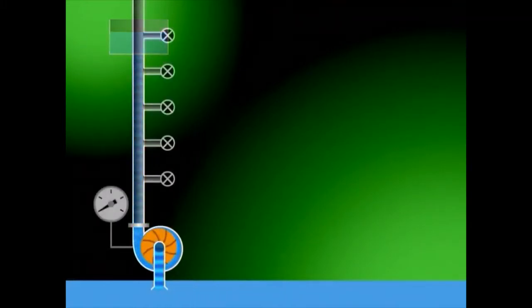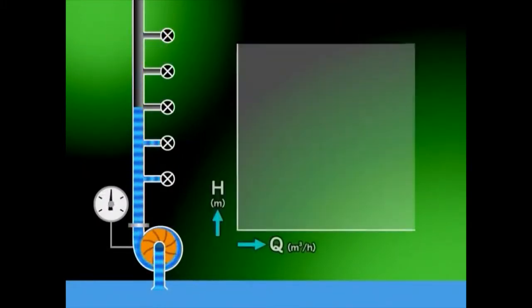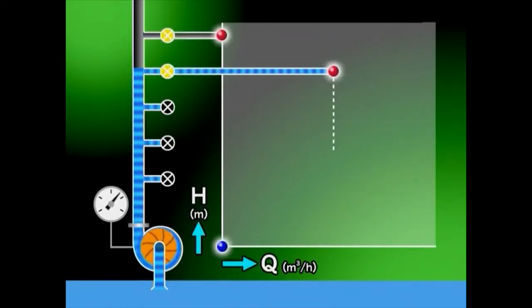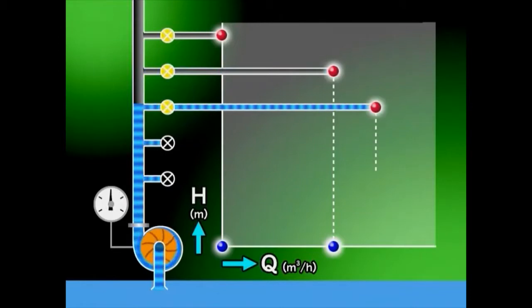A pump's performance capability can be expressed in terms of relation between total pump head, H, and discharge amount, Q. As shown in this graph, the points where the total pump head and the discharge amount cross form a curve peculiar to each pump.